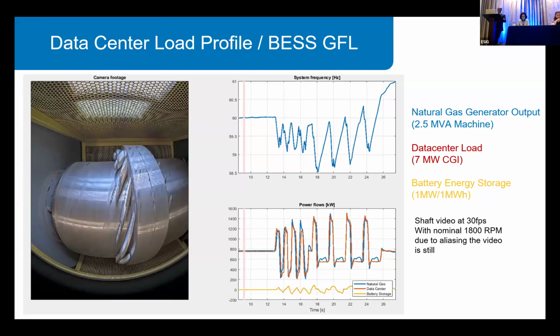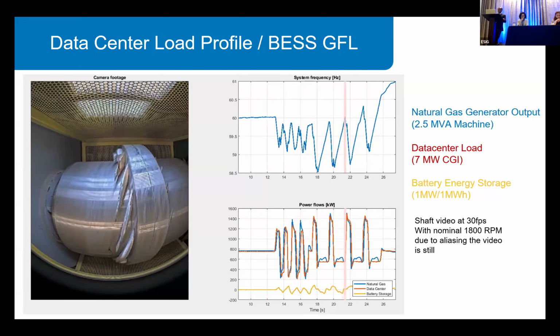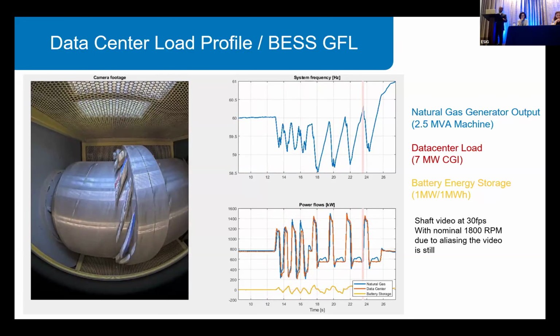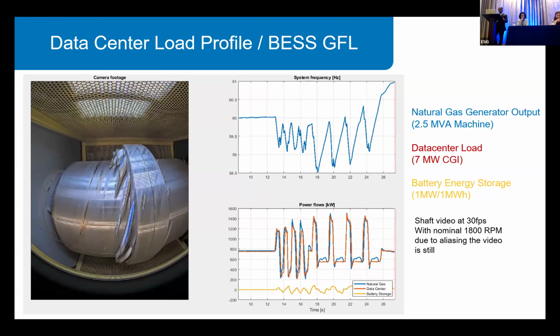Without any compensation for the load, if I just run it, you can see there's a natural torsional oscillation impact on the generator. This is just trying to show what a data center load would do to a natural gas generator sitting close by in electrical proximity.